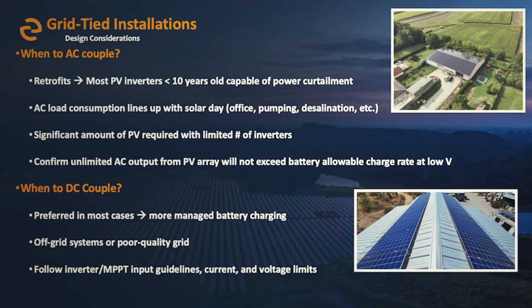AC coupling, DC coupling, right? If you're adding batteries to an existing grid tie system, you can do AC coupling. That just basically involves adding a battery inverter and connecting its AC output with that of your grid tie system. Most PV inverters nowadays can do power curtailment, and they work just fine with that. But I think that's a good option if your load consumption lines up with the solar day. So for example, an office, water pumping, desalination, like if you can satisfy all your loads with that solar output during the day, AC coupling is generally completely fine.